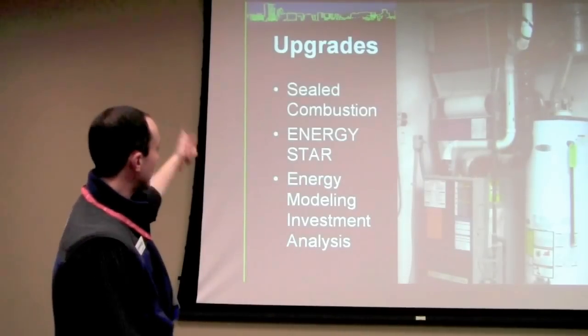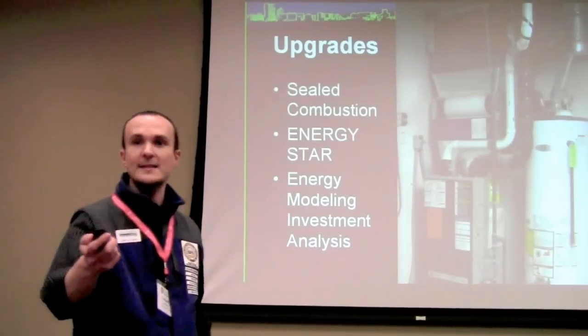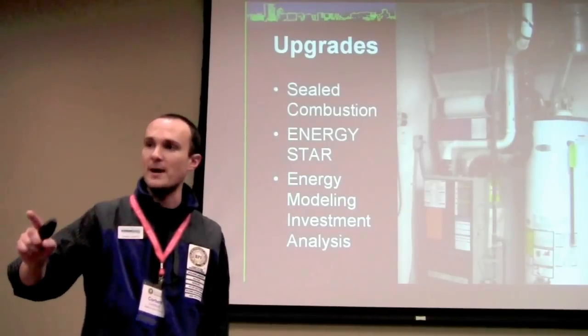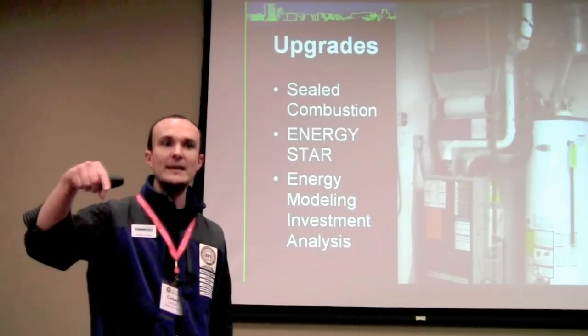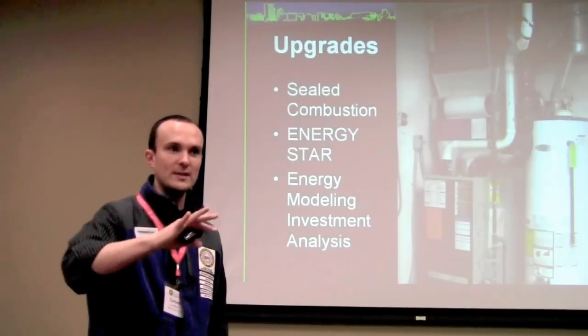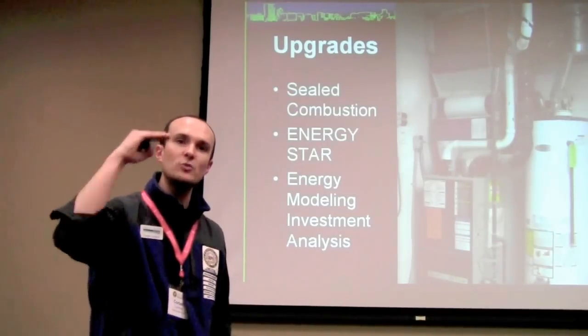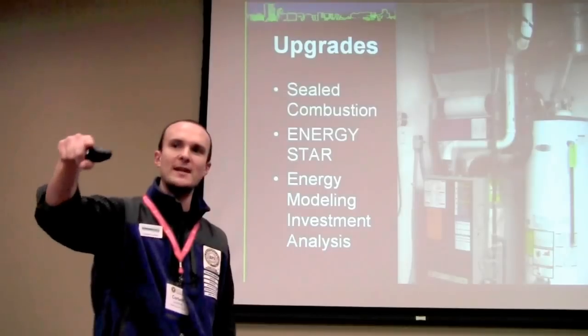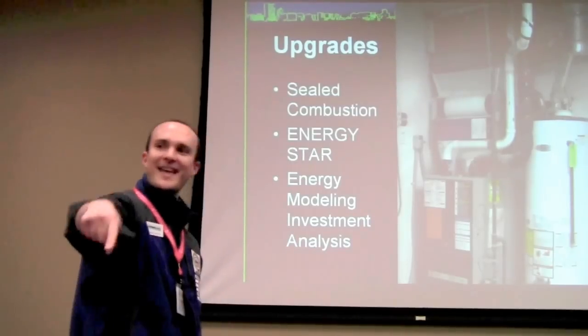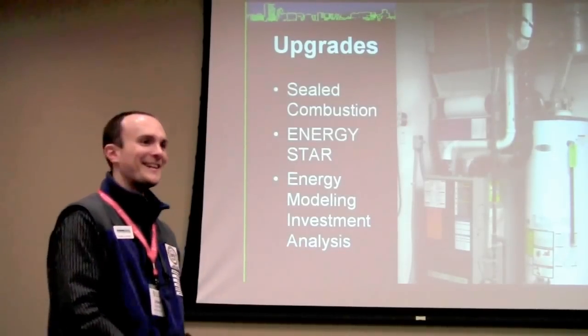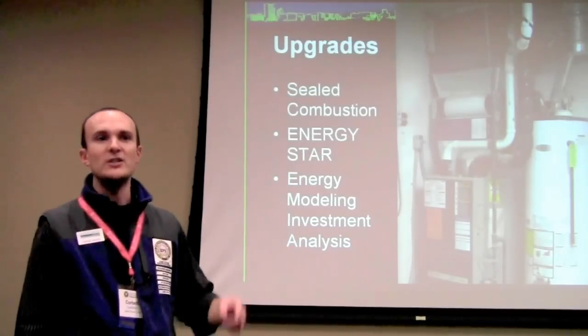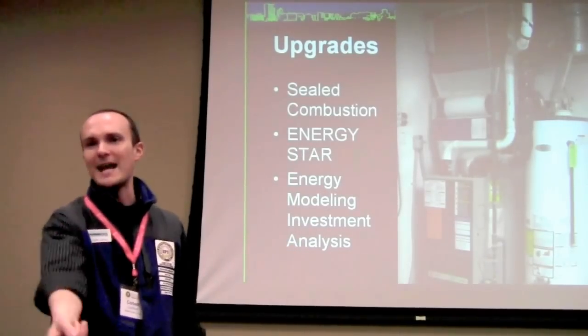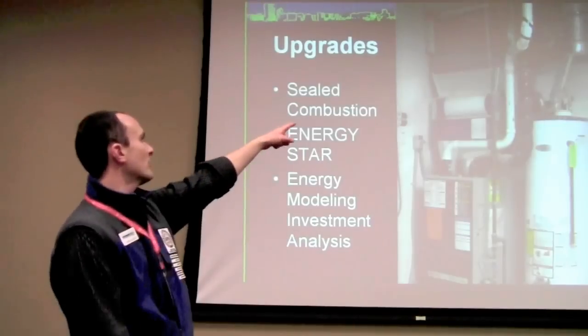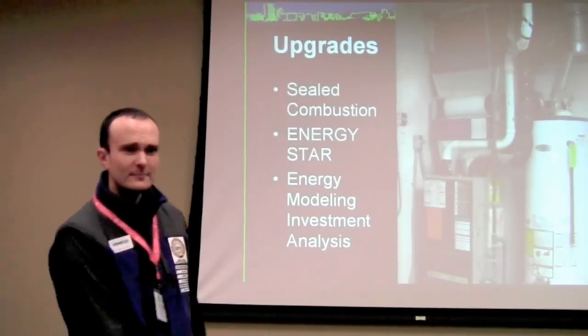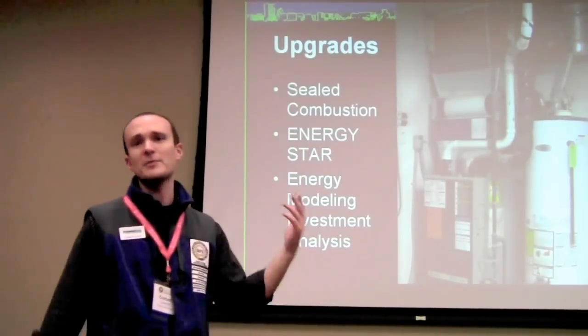I'm going to go for Energy Star if we can, and if you're going to do an improvement analysis, the only way to do it is with an energy model. That's why a system like the federal government's, or a utility system that rebates for individual pieces of equipment, makes how much sense? None! It makes no sense. You take an 80% furnace, replace it with a 90% furnace, you've totally orphaned your water heater, and you've plugged it into a duct system that's only 50% efficient.